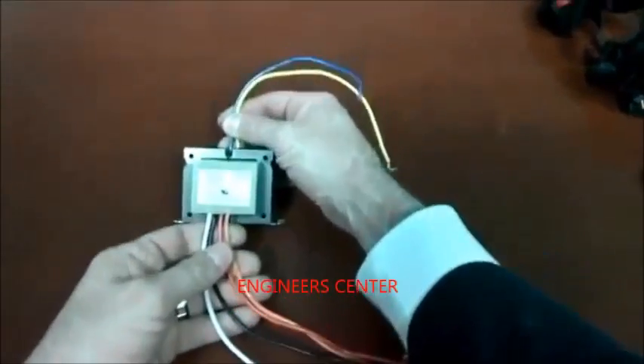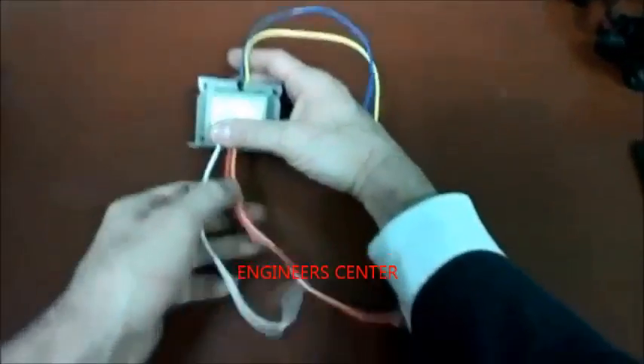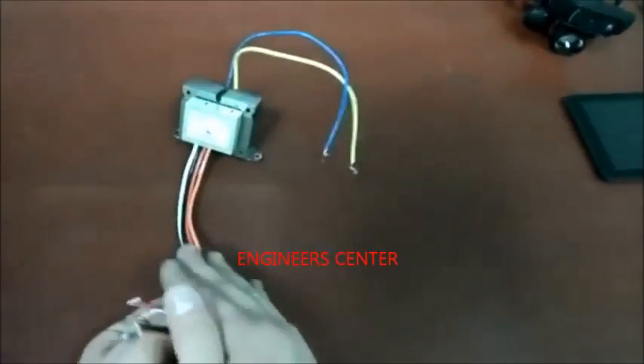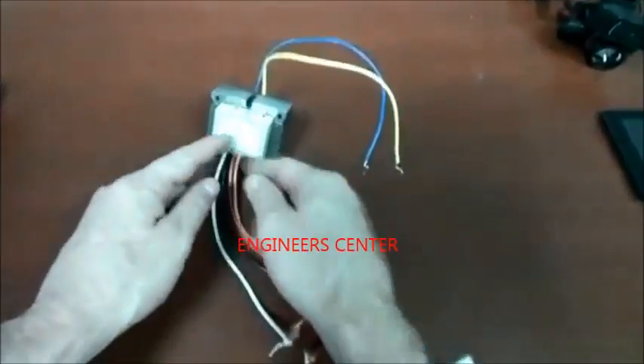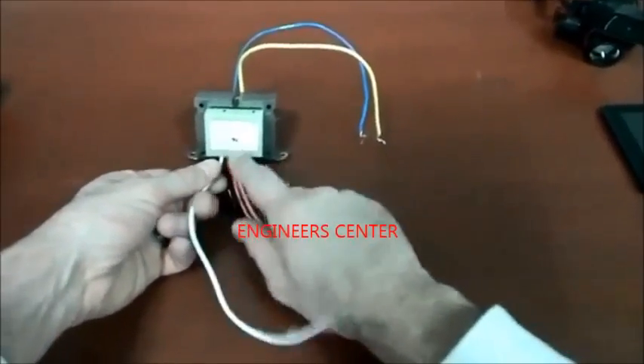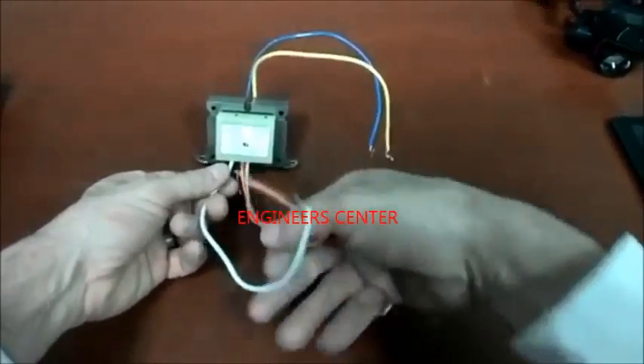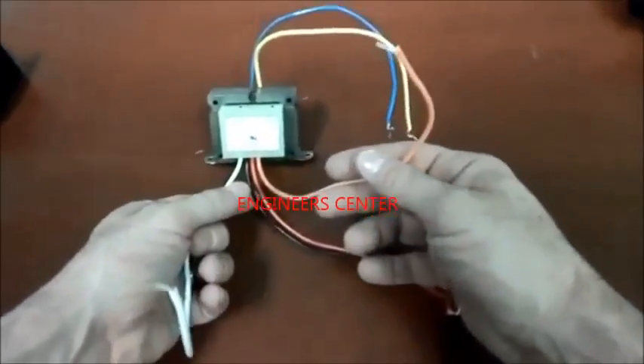Here we have a transformer. So it's not quite a relay now. We have something different, but you've got to know what it does in order to troubleshoot it. Once again, you've got to understand how parts work. This gets voltage and transforms it because it's a transformer. So you just wire the voltage going in, and the output's going to be 24 volts. And so if you have high voltage going in, you have 24 volts coming out. You've got to make sure you're wiring on the right wires, though. And so if you're going outside at the condenser, you're going to probably go white and orange, which you're very rarely going to do. So more than likely, you're going to go white and black in the furnace, and then send that to your board for your 24 volts.